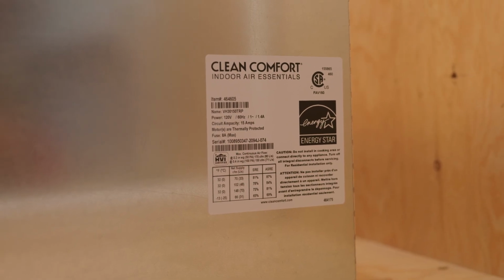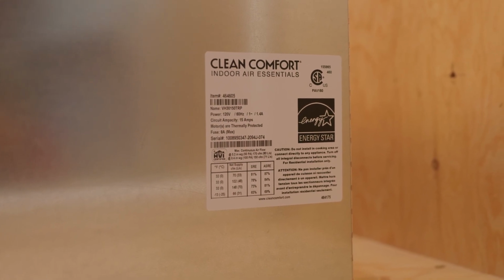One of the things that builders need to be able to read and look at for this type of equipment is the efficiency label, which is located either under or on the side of the unit. The average home in Kelowna that's built, a custom home, is over 3,000 square feet and generally has 4+ bedrooms. That means we're going to have to supply 90 CFM or more of continuous ventilated outdoor air to maintain the indoor air quality. That's a code requirement, so we have to make sure that we're understanding the efficiency with which we're doing that. The numbers that you're seeing on these labels are sensible recovery effectiveness. So what does that mean?